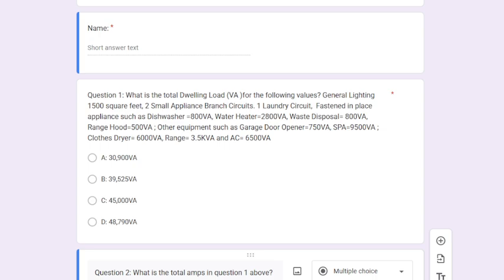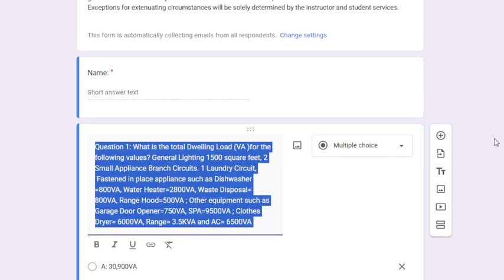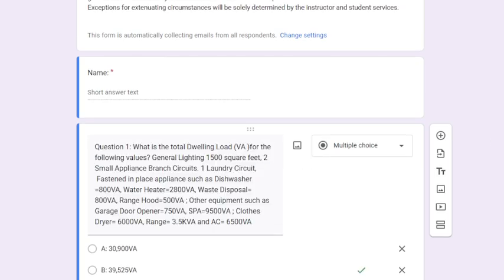Mr. Perez: Yes, the range hood and the range are separate. So do we want to count the range as part of the appliances or combine it with the range? No, the range goes into the range article, table 220.55. Okay, so we'd add them together and then it's 75% of that, right? No. This range hood is, whoops, sorry about that. That range hood is separate from the range. Okay. Yeah, range hood is separate from the range.